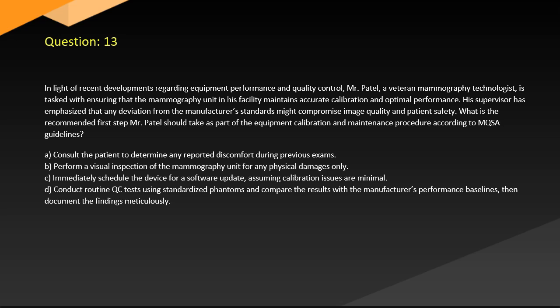A. Consult the patient to determine any reported discomfort during previous exams. B. Perform visual inspection of the mammography unit for any physical damages only. C. Immediately schedule the device for software update, assuming calibration issues are minimal. D. Conduct routine QC tests using standardized phantoms and compare the results with the manufacturer's performance baselines, then document the findings meticulously.